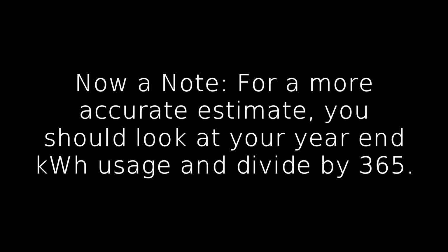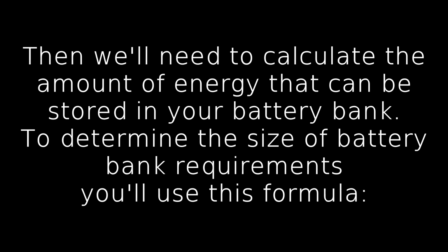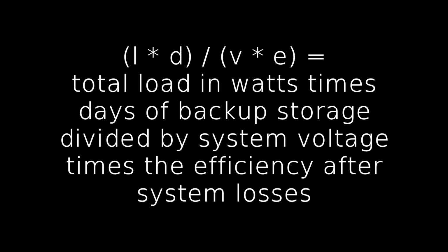Then we'll need to calculate the amount of energy that can be stored in your battery bank. To determine the size of your battery bank requirements, you'll use this formula: total load in watts times days of backup storage divided by system voltage times efficiency after system losses.